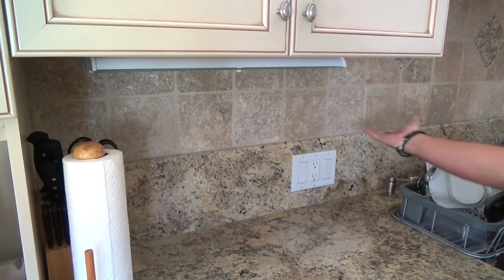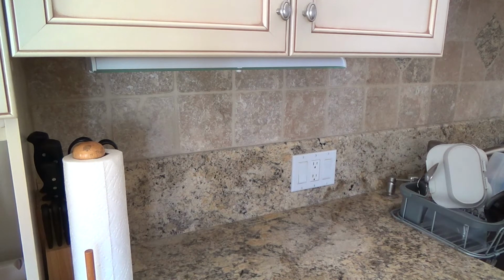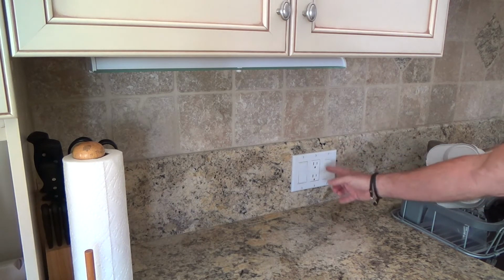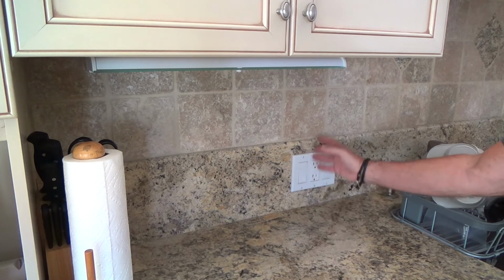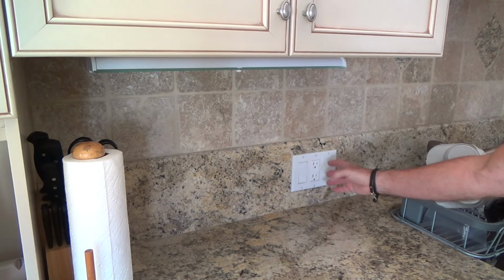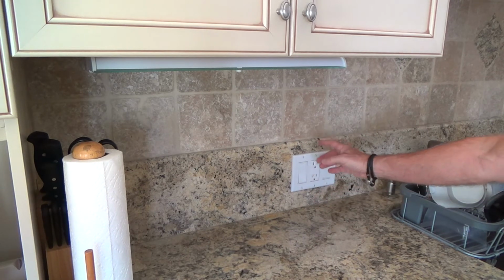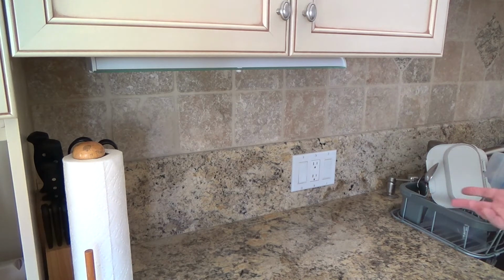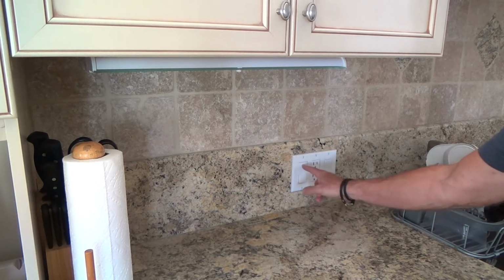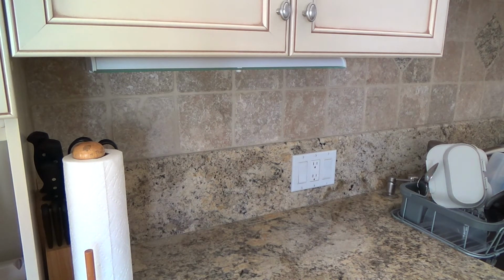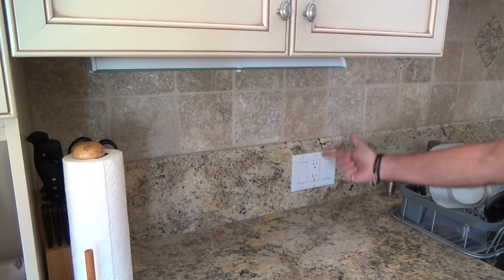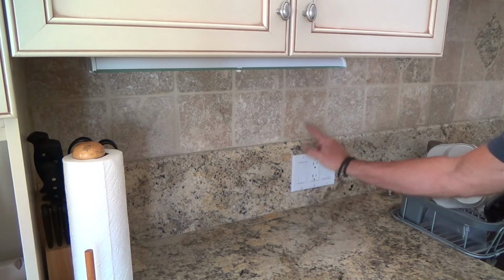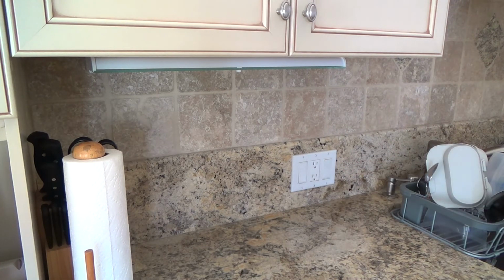The main reason is that if somebody else is working in here, they don't want them confused about how things are wired, because standard practice is all your light switches are on one circuit, your outlets are on different circuits, and your garbage disposal is usually on a separate circuit—or maybe tied in with the microwave or dishwasher. Here they decided on one dedicated circuit for the garbage disposal. Could they have used just one circuit for everything? Maybe, but that's just not how electricians generally do it. So that's why you have to go through the thought process, especially in the kitchen.